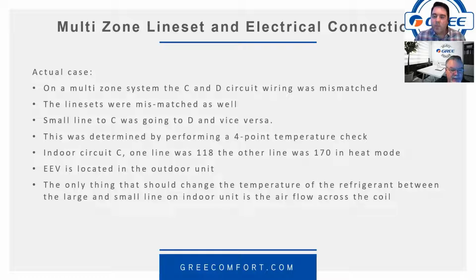So indoor circuit C, you said that you did a 4-point temperature check. Yes, a 4-point temperature check, and I think we'll talk more about the 4-point temperature check. But basically, once we've ruled out all of the basics, dirty coils and all the stuff we went over, all the visual checks, this is a good check to see if there's a restriction anywhere. Right. And the key on the mismatched refrigerant lines going to the wrong ports was that the temperature on one pipe compared to the other one was way different. The one that was calling and the one that wasn't calling, the one that wasn't calling was getting refrigerant to it when it shouldn't. So you're seeing heat there in the heat mode.